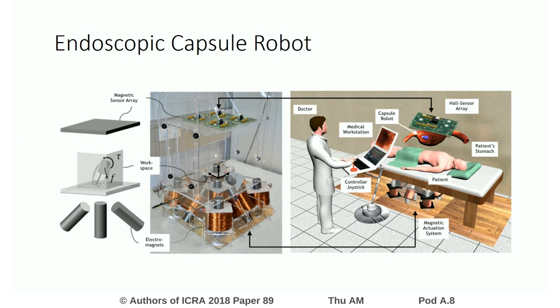Our capsule prototype is a magnetically actuated soft capsule endoscope, which is designed to be used in the upper gastrointestinal tract for disease detection, drug delivery, and biopsy operations. The prototype is composed of an RGB camera, a permanent magnet, and a drug chamber. The magnet produces force and torque in response to a controlled external magnetic actuation field.